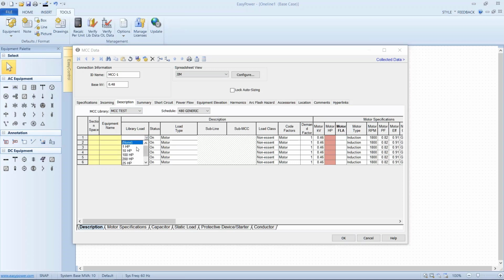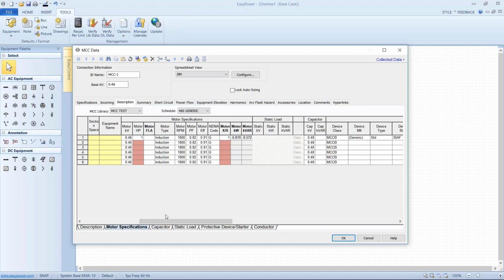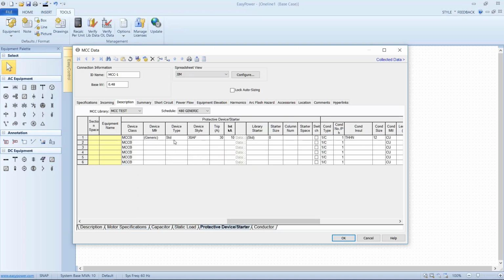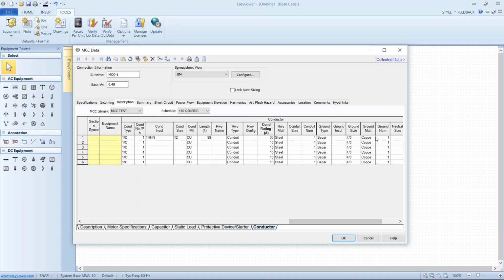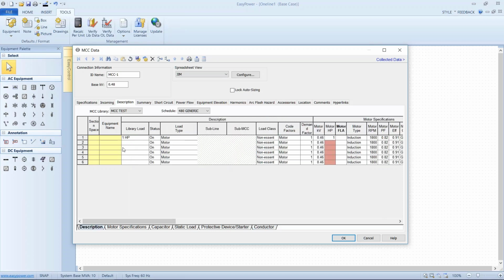And so now when I pick out a load from that list, I can say, okay, in the 1 horsepower, and it fills in, if you scan across here, the motor specifications, the X over R calculations, the protective device that I would normally use. In this case, I'm selecting generic. And then I've designated 99 feet as I would see from the smart design, and I'd go back and update that once I got the as-builts. So consequently, I can go through and populate my motor control center very easily, and do so with the knowledge that I've already considered what the ramifications are of the loadings that were taking place.